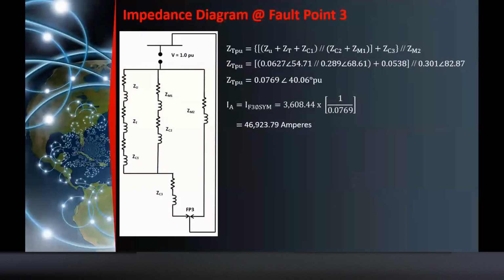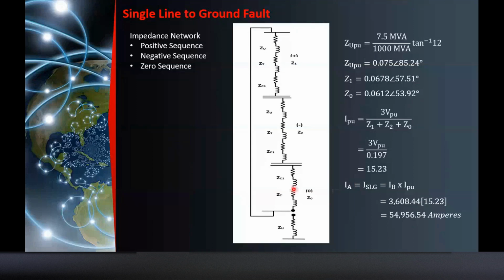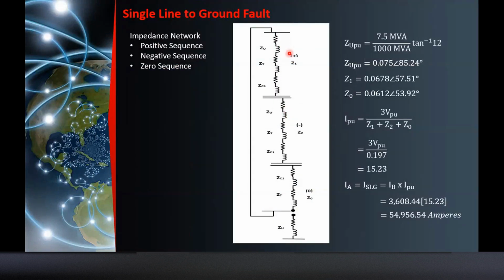So basic lang yung ginawa kong presentation. Then next, single line to ground fault. Sabi natin sa single line to ground fault, this is an unbalanced fault. So mag-i-exist na yung 3 sequence network. The positive, negative, and 0. Okay, tatandaan natin, transformer is the same. Z1, Z2, and Z0. Utility is the same. Cable is the same. So based sa fault point 2, kanina, saan tayo kumuha ng fault? Doon sa main bus. Main bus na lang ang kinuhanan ko ng fault. So ito yung impedance diagram niya. ZU, ZT, and Z cable 1 will be your positive sequence network. ZU, ZT, Z cable 1, your negative sequence network. So, tatlo kasi yung mag-i-exist. Isipin nyo, i-visualize nyo na pag nagkaroon ako ng fault do sa 400 volts, single line to ground fault, ito yung impedance diagram niya.